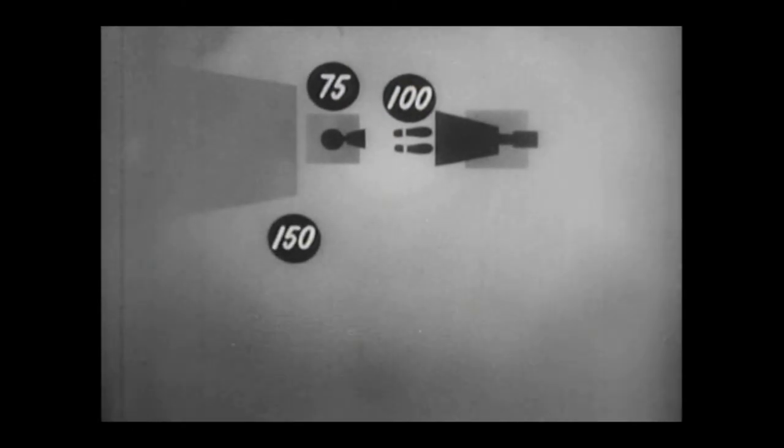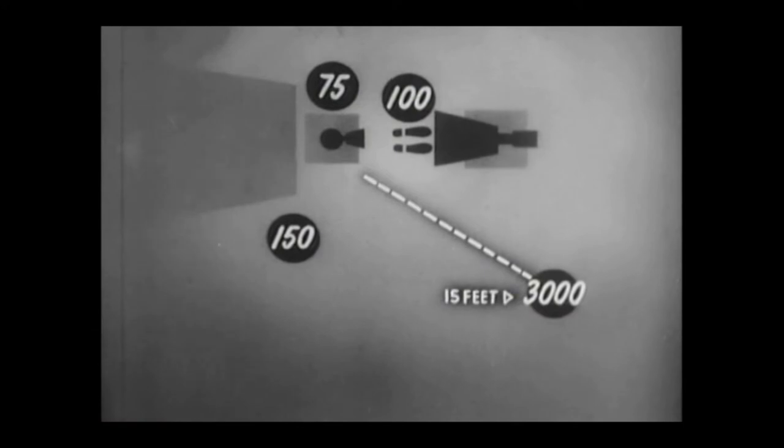A careless person standing beside the tube would exceed safe radiation after only 75 films per week. Standing beside the patient, he would exceed the limits of safe radiation after only 100 films. A careless person standing beside the lead screen could take only 150 films a week before he exceeded three-tenths of a roentgen. Even at a position 15 feet from the x-ray tube, he'd be in danger after 3,000 films.